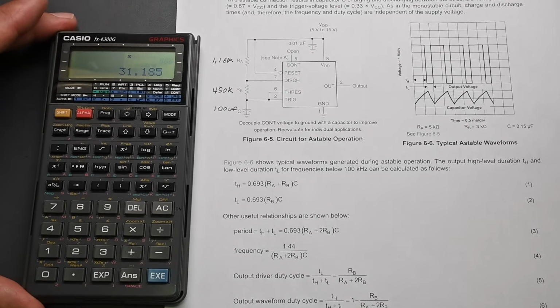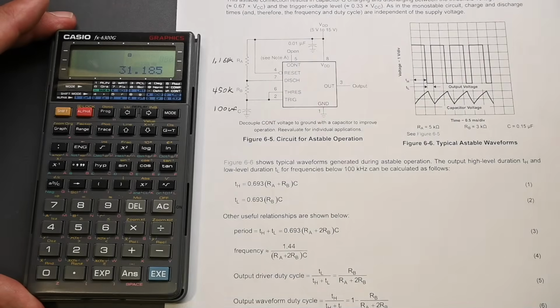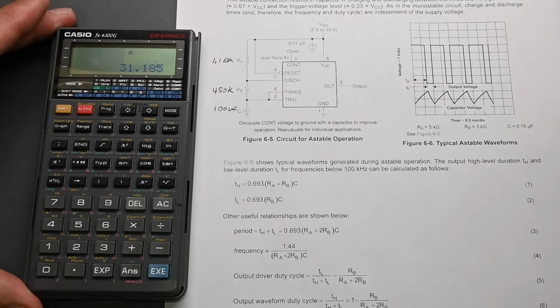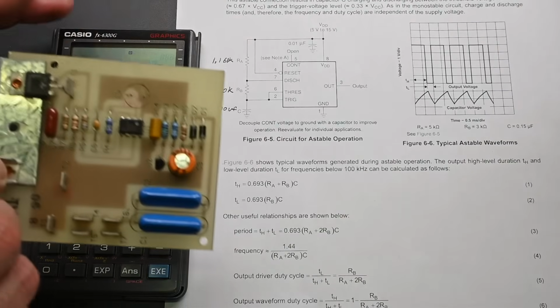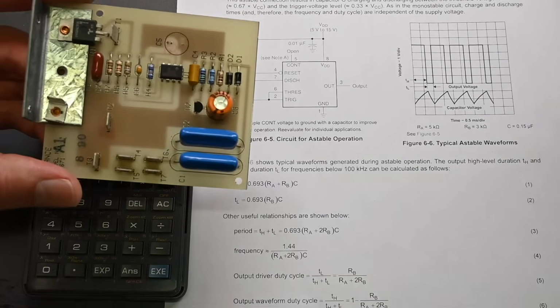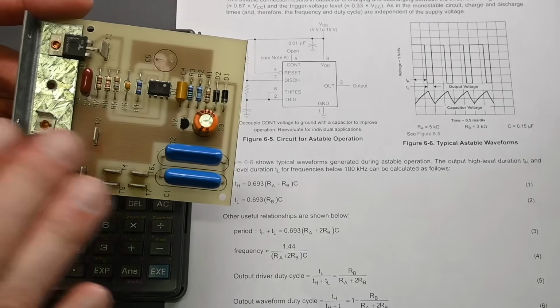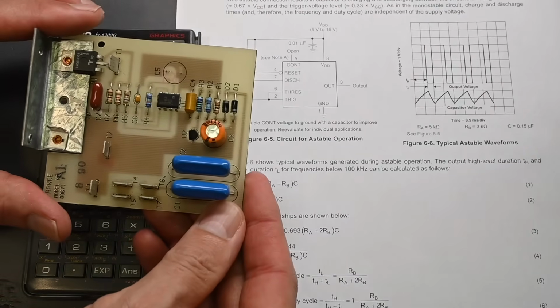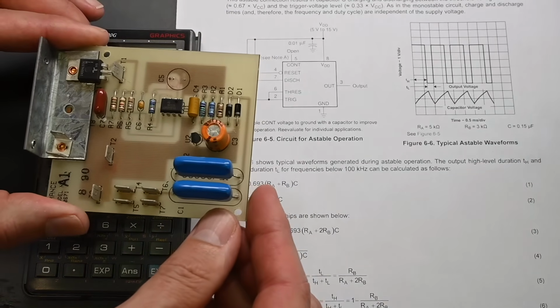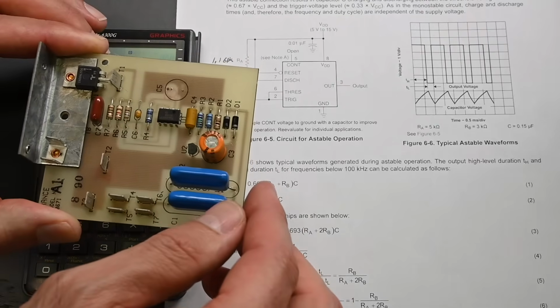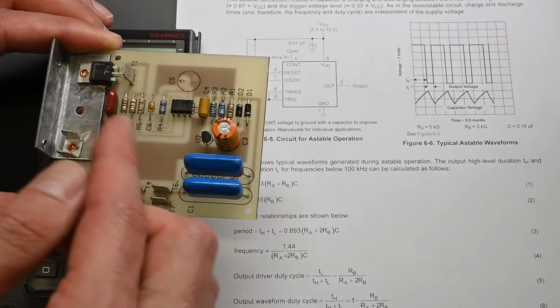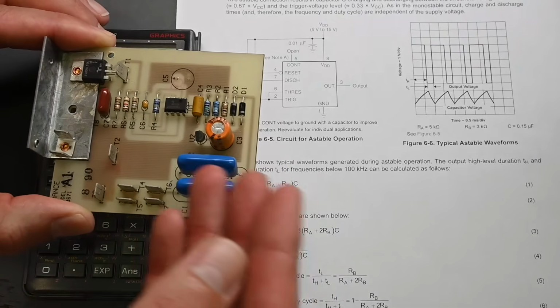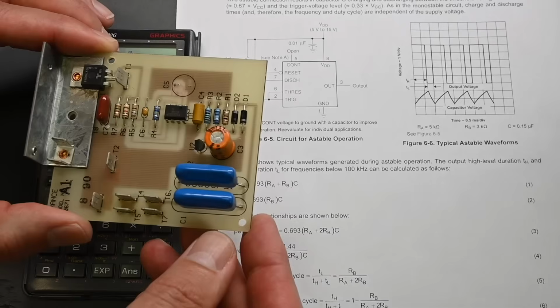Definitely a 50% duty cycle, so no problems there — that's exactly how we were seeing this operate, on for about 30 seconds, off for about 30 seconds. So this circuit board is definitely working correctly; there's nothing wrong with it, no failed components. We just need to modify the value of this capacitor so it runs a little quicker. The owner of the sign said about 10 seconds on and off would be ideal.